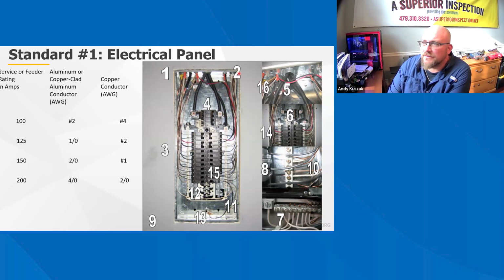Number 2, over here on the right. Only one service should be installed for each dwelling or building. A minimum 100 amp service is needed for a single residential dwelling unit. Number 3, the service panel is not allowed to be located inside a bathroom, over stairs, or inside a clothes closet. Just keep in mind that homes were built before electrical code standards, and so you will often find electrical panels in places that today would not be recommended.